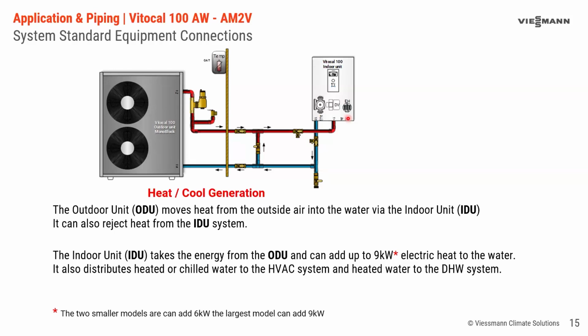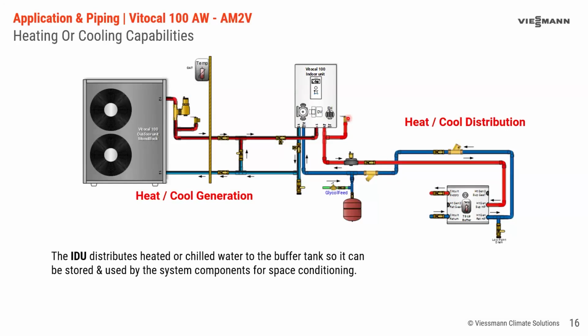Now where does that go from there? Well, it goes to the distribution system, which is the buffer tank. So when it's in a heating application or a cooling application, the diverter valve sends water to the buffer tank through these two connections here. And then this becomes your stored energy.